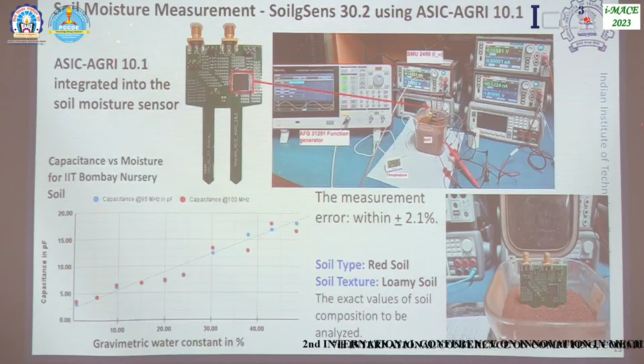But now, just to show you how important frequency is, we did this measurement on purpose. These are the measurements actually performed and then back-calculated to the capacitance. One is at 95 megahertz and one is at 100 megahertz. As you notice, at low values of moisture, because the amount of water is low, 95 and 100 megahertz don't make a big difference. As you increase the amount of water, say between 20, 30 to 40%, it is very important, because that is where you need to decide.